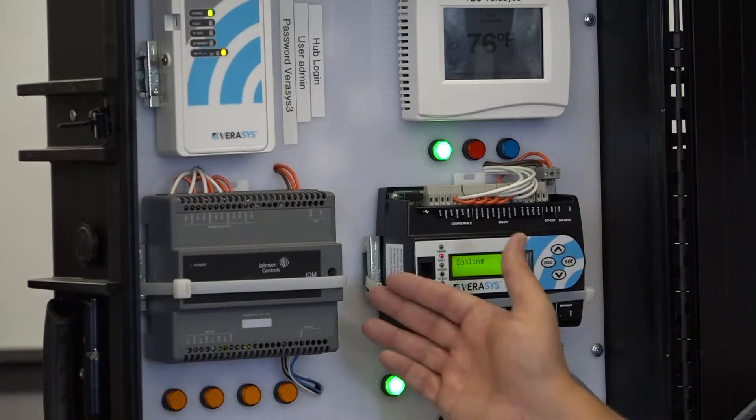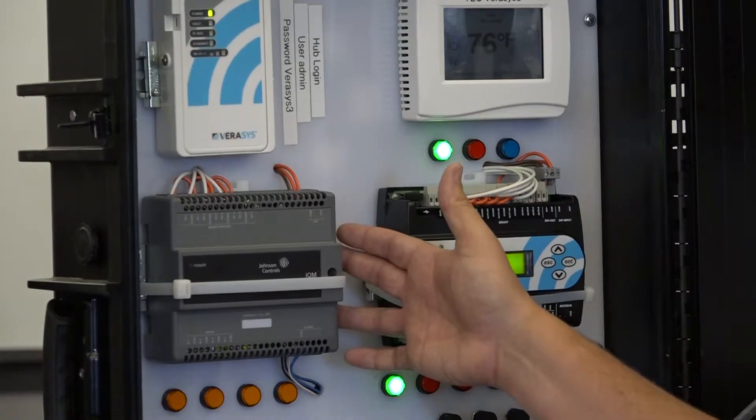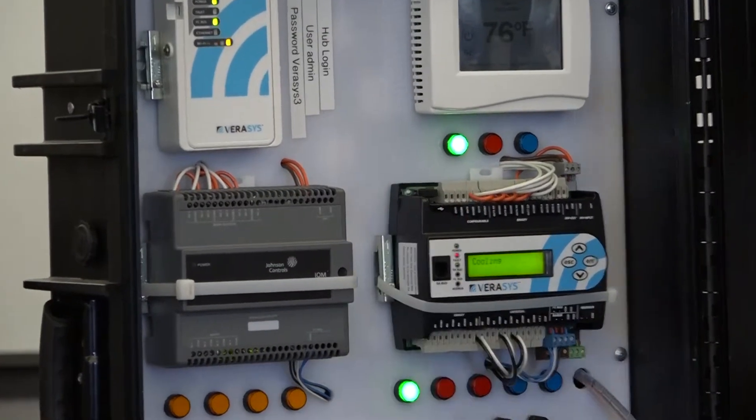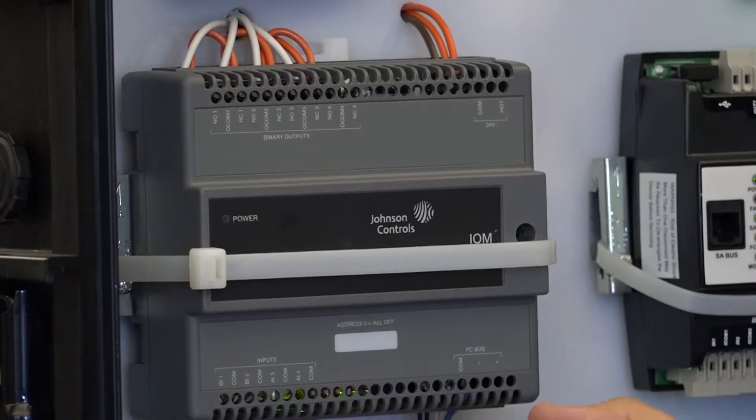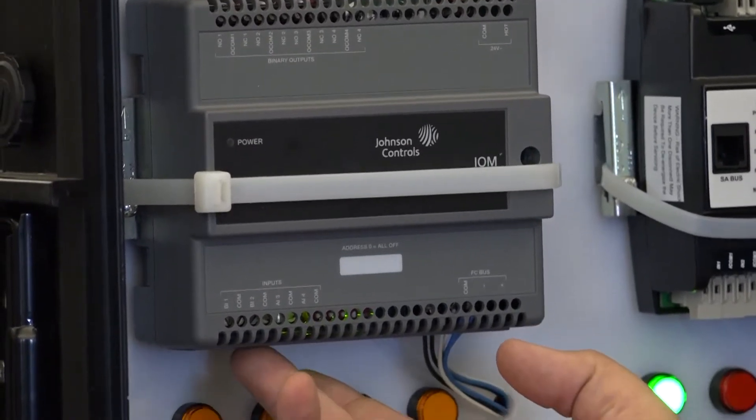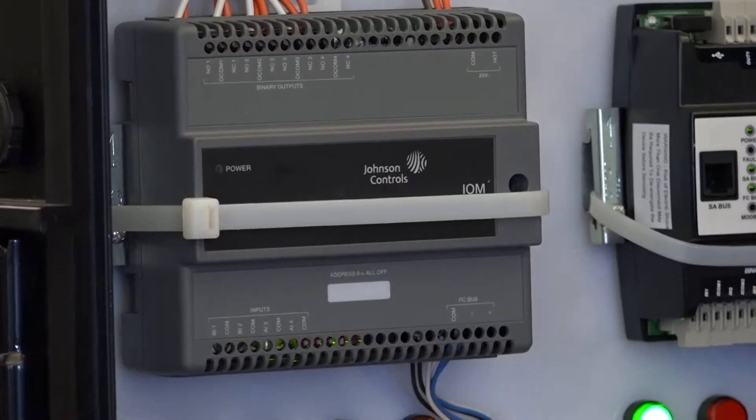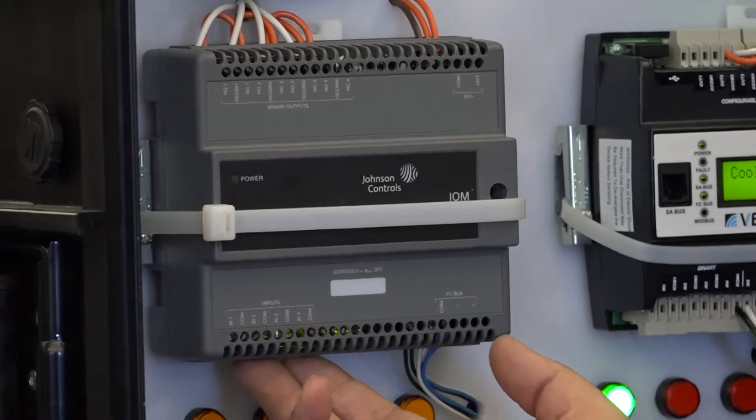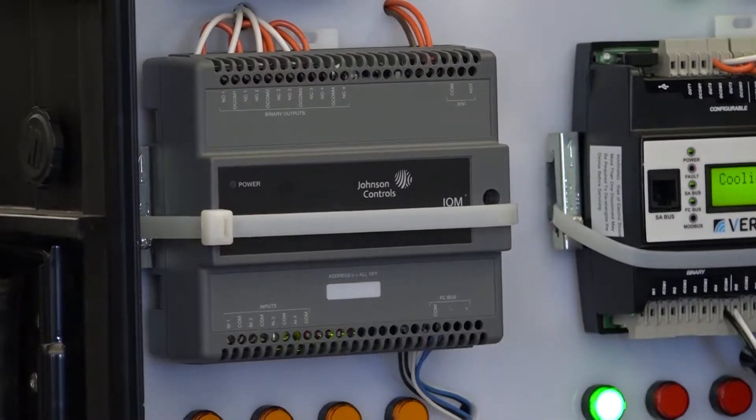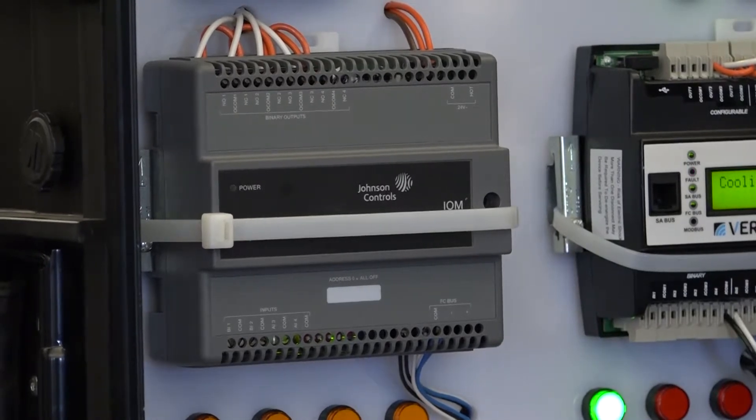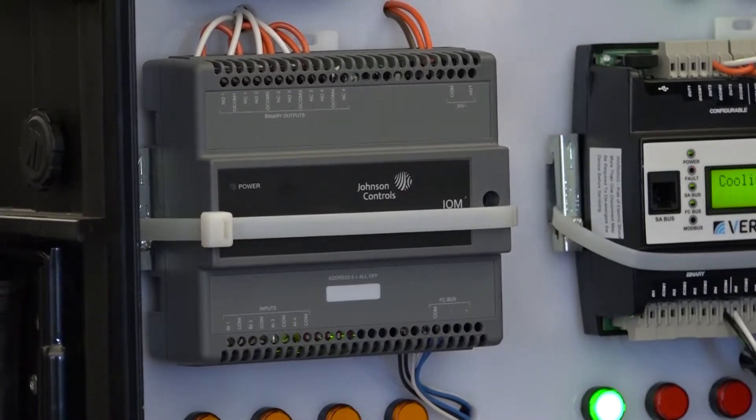The IOM100 is mainly used for simple systems. For example, we could take an outside air temperature sensor and either bring it off a controller or hardwire that sensor into the IOM and use it with an interlock to control or enable a boiler.